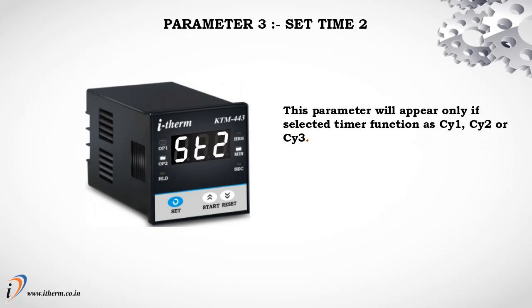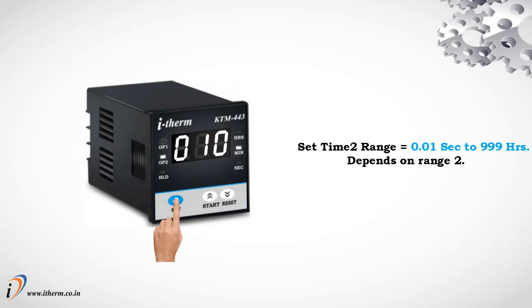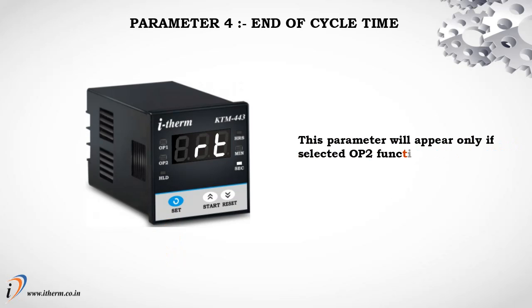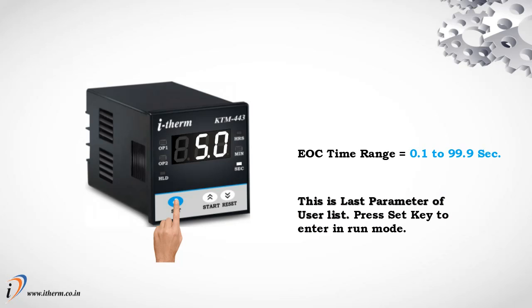Parameter 3: set time 2. This parameter will appear only if the selected timer function is cycle 1, cycle 2, or cycle 3. For cycle 1, sets the on time for output 1. For cycle 2, sets the off time for output 1. For cycle 3, sets the reverse time for output 2. Set time 2 range: 0.01 seconds to 999 hours, depending on range 2. Parameter 4: end of cycle time. This parameter will appear only if output 2 function is set to end of cycle. End of cycle time range: 0.1 to 99.9 seconds. This is the last parameter of the user list. Press the set key to enter run mode.